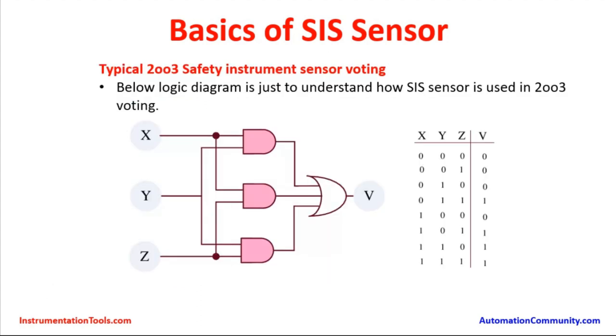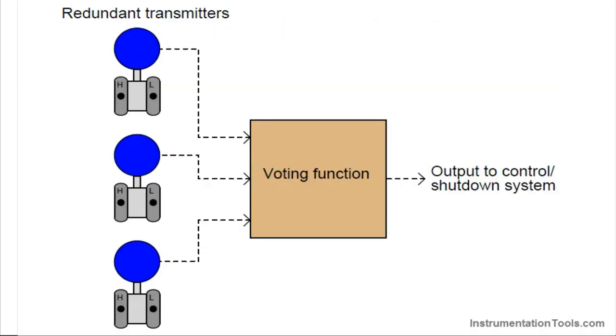Here we are seeing a logic truth table for a typical two-out-of-three safety instrumented sensor voting. The process requirement may be very high accuracy based on the process and the size of the equipment being protected — such as a boiler, distillation column, or high-pressure piping protected against hazards by safety instrumented systems. There will be three transmitters to measure the pressure, or level if it is a vessel, or temperature.